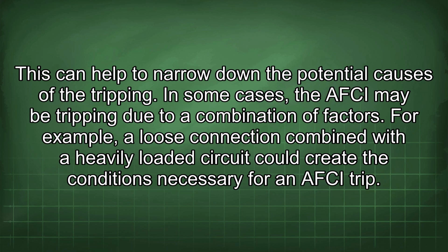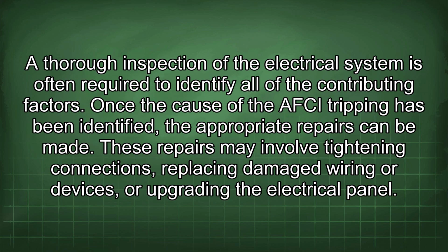In some cases, the AFCI may be tripping due to a combination of factors. For example, a loose connection combined with a heavily loaded circuit could create the conditions necessary for an AFCI trip. A thorough inspection of the electrical system is often required to identify all of the contributing factors. Once the cause of the AFCI tripping has been identified, the appropriate repairs can be made.